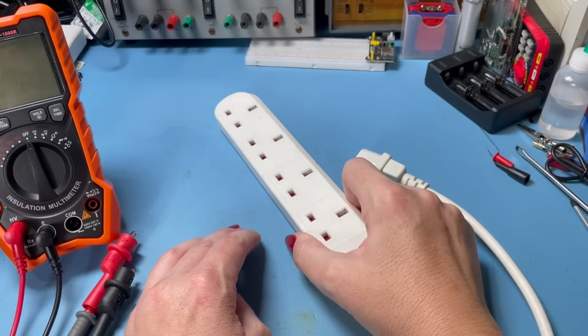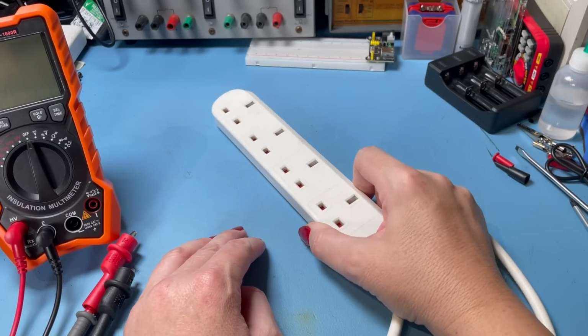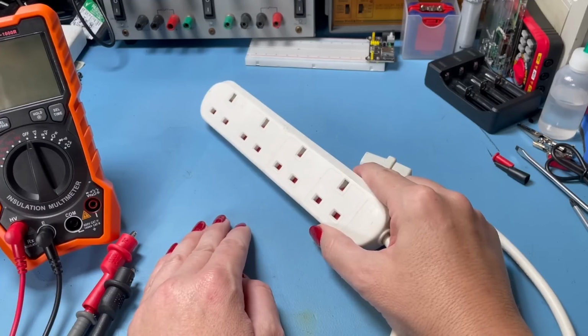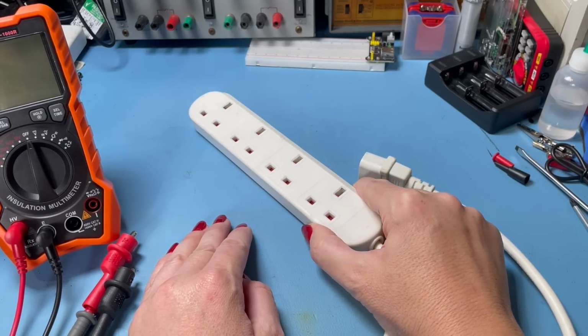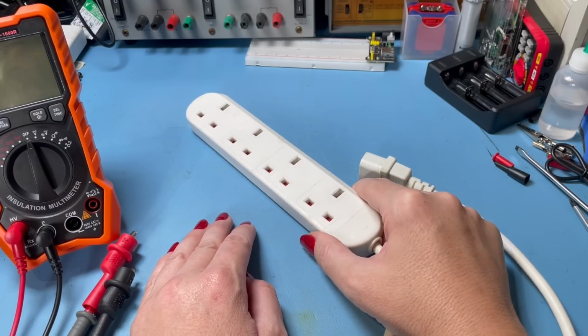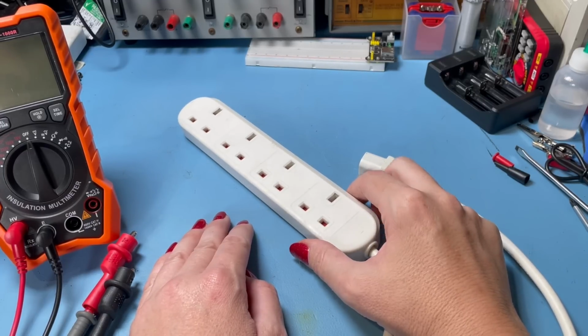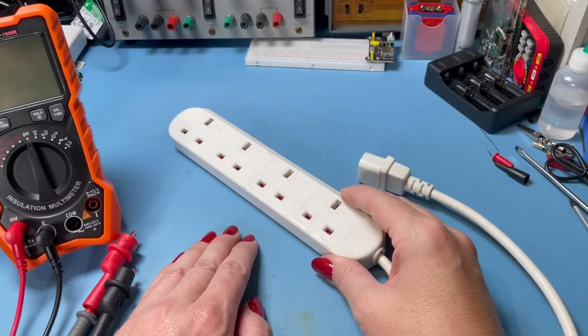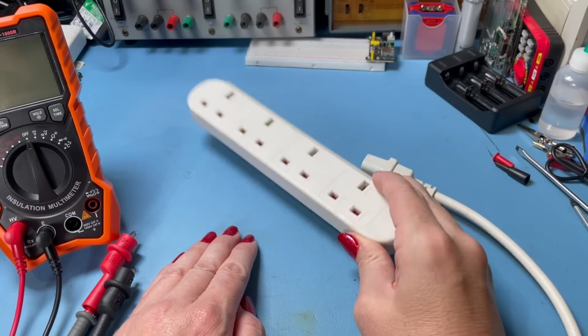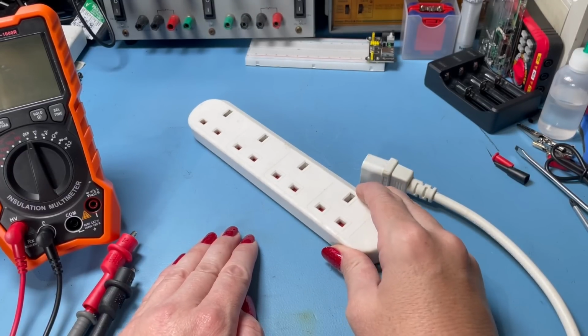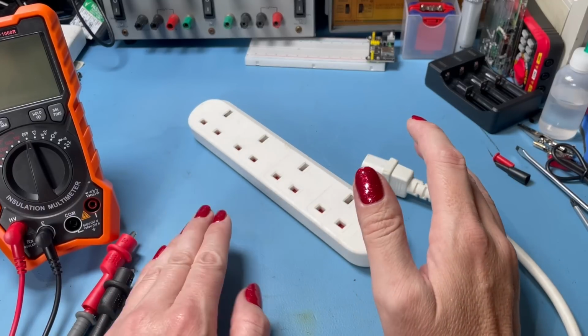It's just a standard 4-way extension lead. Now, in terms of test voltage, in a PAT test, a class 1 test, you'd be testing normally at 500 volts, which is the default for the PAT tester. So you want to be testing above the insulation rating. This is rated at 250 volts. We want to be testing at 500 to stress it out to see if it's going to fail or not.